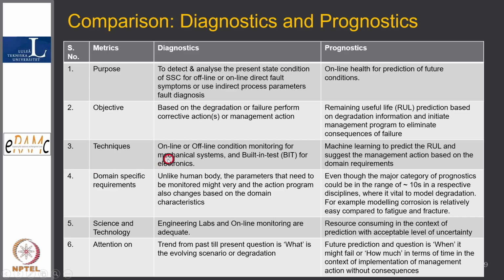Both online and offline techniques exist for diagnostics. For electronics, there is a built-in test facility provided online, instrumented so that we know a fault exists. A short impulse of microseconds is sent across so that the relay or actuator will not come into action and disturb the process. Actuation of the final relay requires a signal of more than 30 microseconds, so in 1 or 2 microseconds that signal is sent without disturbing the electronic card, allowing us to know its condition.